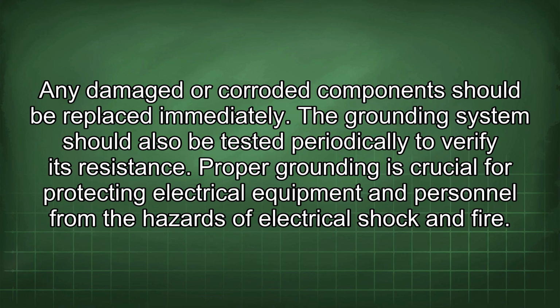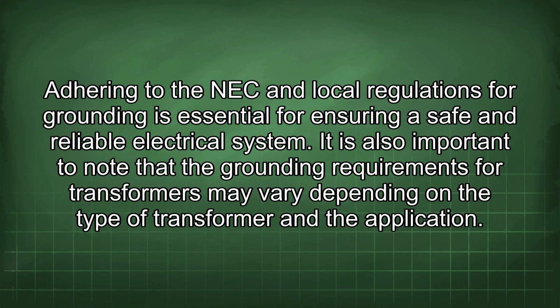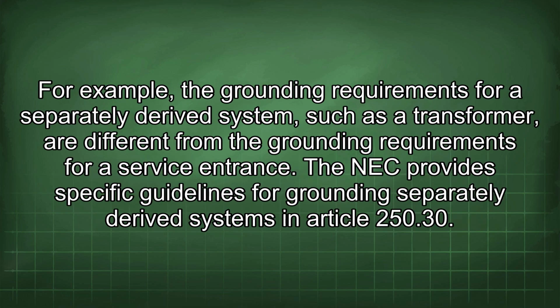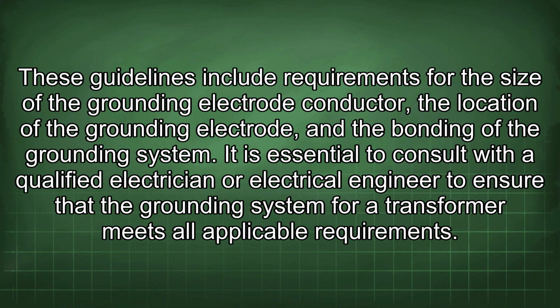Proper grounding is crucial for protecting electrical equipment and personnel from the hazards of electrical shock and fire. Adhering to the NEC and local regulations for grounding is essential for ensuring a safe and reliable electrical system. It is also important to note that the grounding requirements for transformers may vary depending on the type of transformer and the application. For example, the grounding requirements for a separately derived system, such as a transformer, are different from the grounding requirements for a service entrance. The NEC provides specific guidelines for grounding separately derived systems in Article 250.30. These guidelines include requirements for the size of the grounding electrode conductor, the location of the grounding electrode, and the bonding of the grounding system.